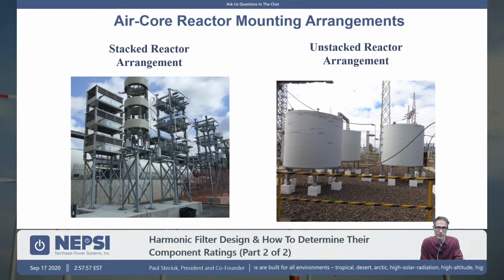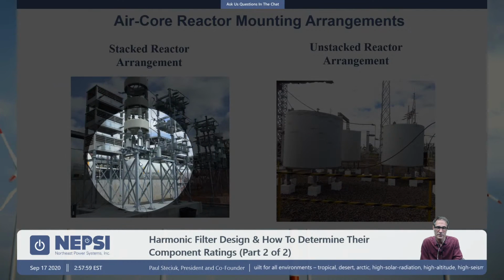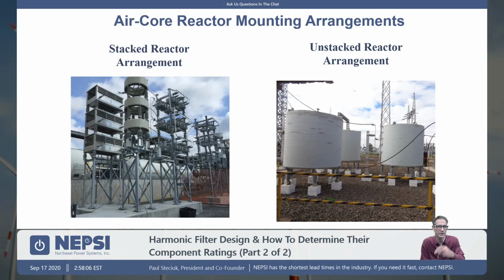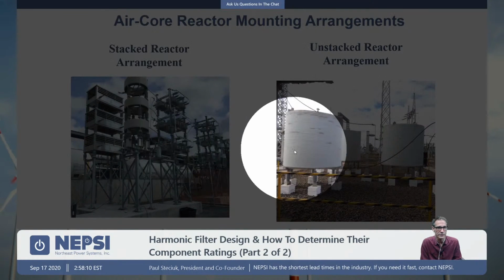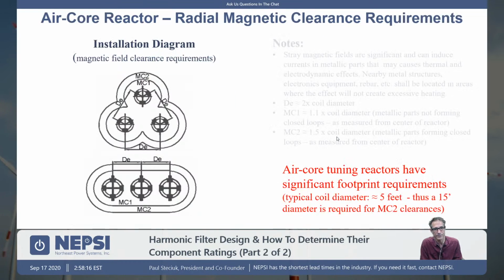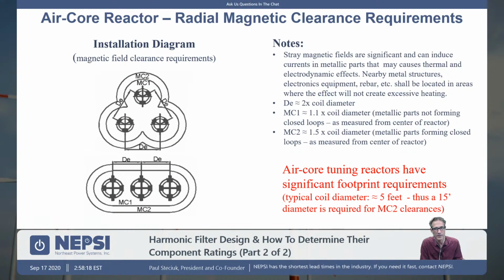You can see here on the left, we got some air core reactors stacked up on an elevating structure. This is a requirement in North America that you have at least 3 meters of height, 9 foot 6 inches. And on the right here are some pictures of some air core reactors sitting at ground level. This is something you would not typically see in North America. And we're kind of running out of time, so I'm zipping through now. These are the air core reactors we're shown.